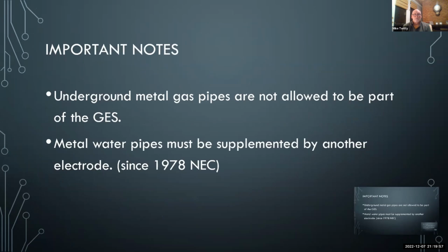All right, metal water pipes must be supplemented by another electrode. All the older houses we used to see, that was the main grounding source, the underground metal water pipes, and it was a great ground rod. But as plastic pipe became prevalent, code started realizing that's going to start getting replaced, which loses the grounding electrodes. So they started saying that it must be supplemented by another electrode.